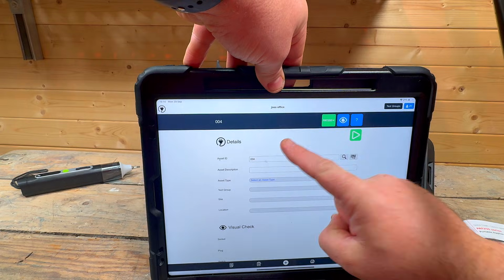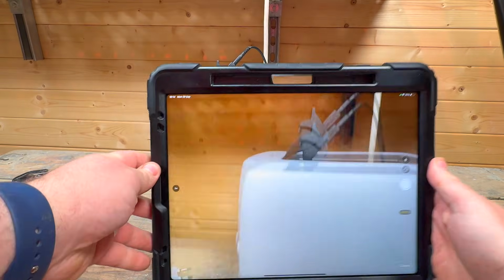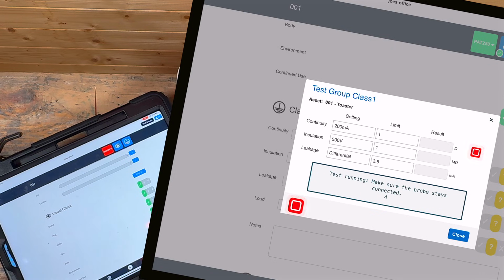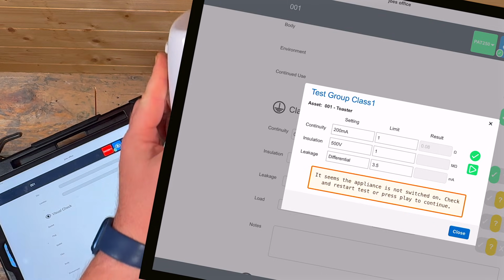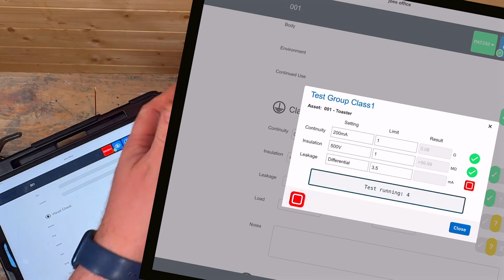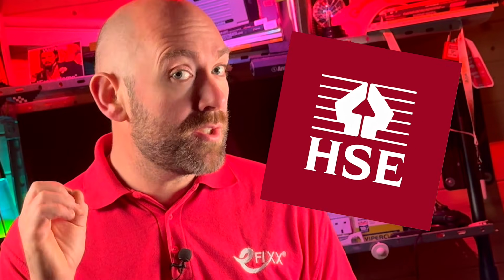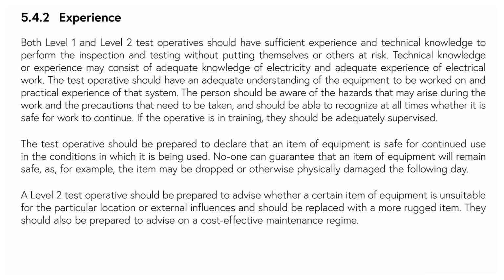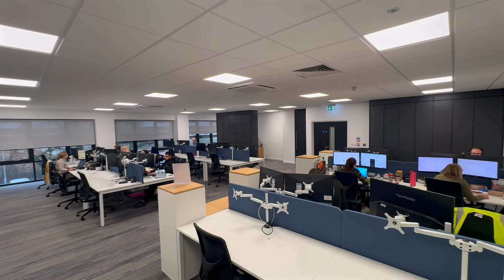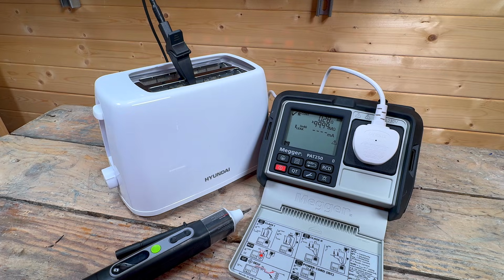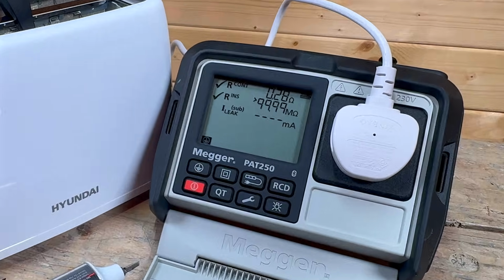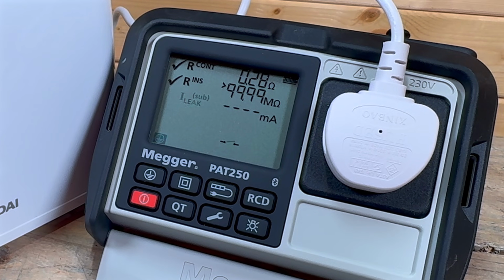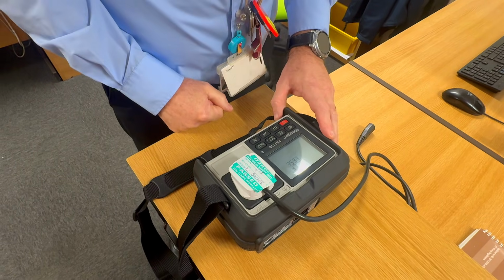A competent operative must also be able to complete records accurately and sign them off. That signature confirms their judgment that the equipment is safe for continued use based on the inspection and tests carried out. This is why competence can't be superficial. So the HSE offers guidance and describes two levels of operatives. A Level 1 operative uses simple pass or fail instruments and does not interpret readings. This is suitable for low risk equipment where there is no disassembly. A Level 2 operative uses instruments that provide numerical values and must interpret those readings.